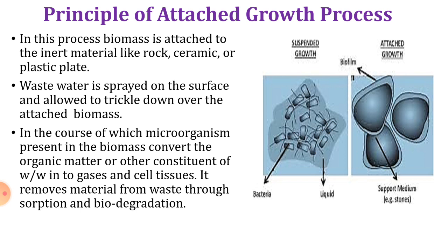Whereas in case of attached growth, there is inert material like stone, rock, around which the biofilm gets created due to the spraying of the wastewater. As the wastewater is sprayed on such inert material, the film is formed. That film is called a biofilm which contains the microorganisms. The microorganisms get attached to the inert material, and from there by the biosorption and the biodegradation they take up the organic matter as food and they stabilize it.